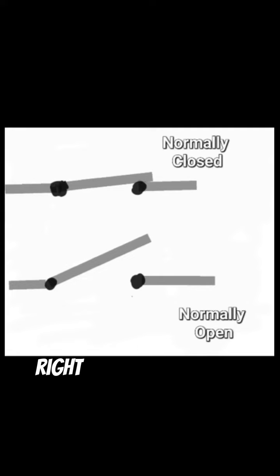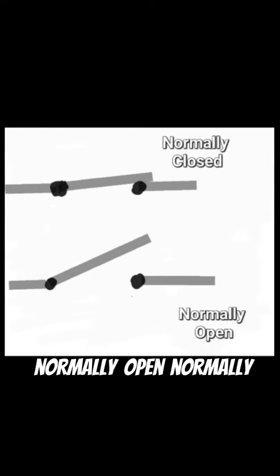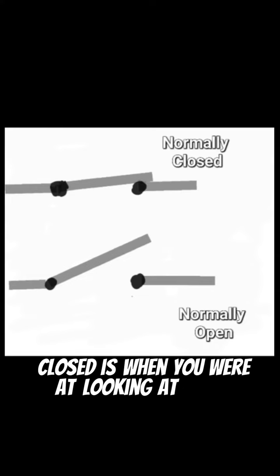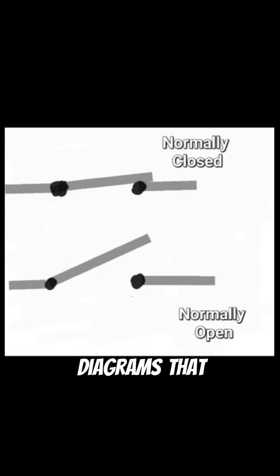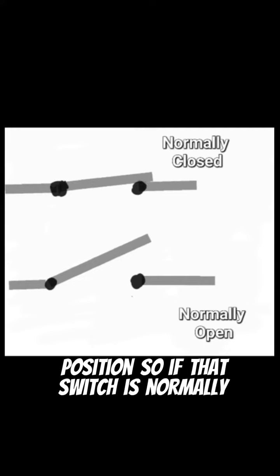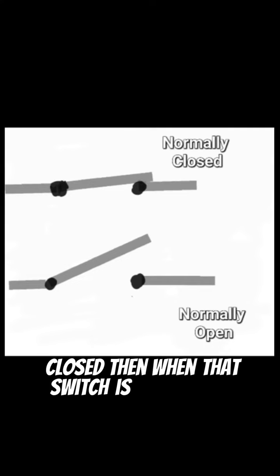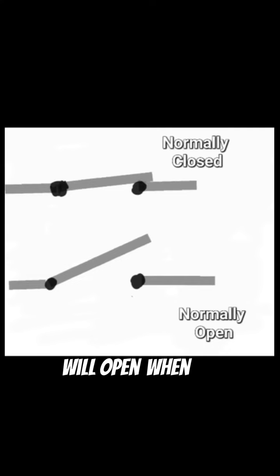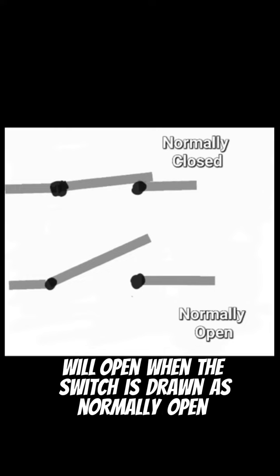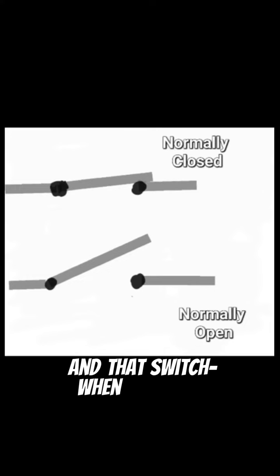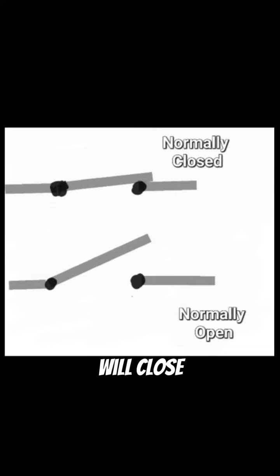So what you're going to see right here is a normally open and a normally closed switch. And what we mean by normally open and normally closed is, when you are looking at those wiring diagrams, that switch is going to be drawn in the normal position. So if that switch is normally closed, then when that switch is activated, it will open. When that switch is drawn as normally open, then when activated, it will close.